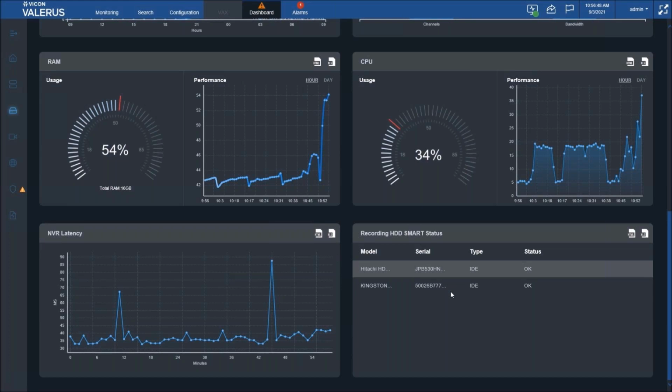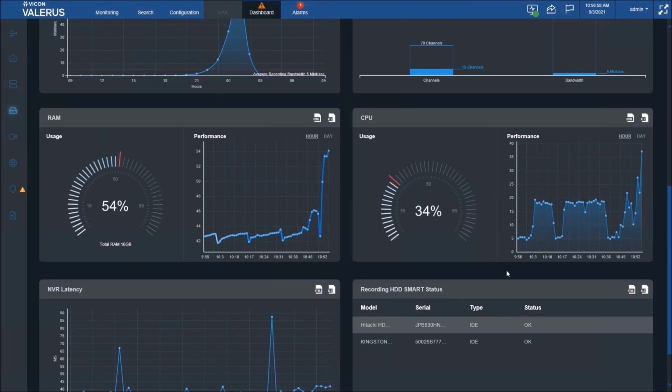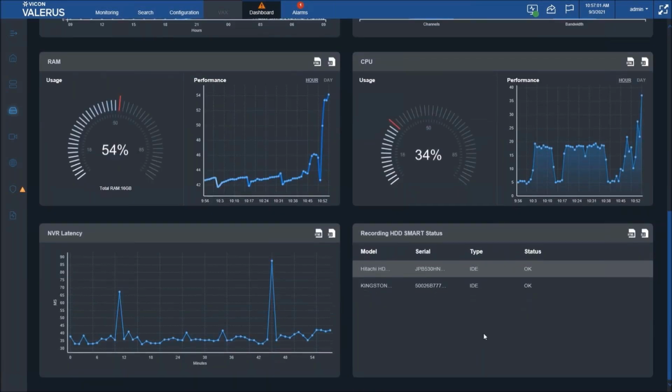And SMART is a piece of software, very, very capable, that runs on the drives themselves. And we can speak to the drive, so to say, and ask it about issues seen on the drive. And the drive will let us know of certain problems that it identifies. It will tell us bad sectors or some things that are going on. And the advantage, we're talking about preventive maintenance: if we know a drive is showing certain behavior problems and it's already showing some bad sectors, it may be going downhill, we can replace the drive before it fails completely. So this is a very nice indicator. Right now, everything is showing okay, but it may not be the same later.